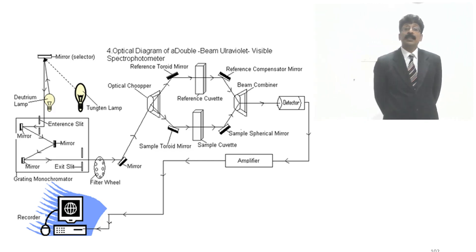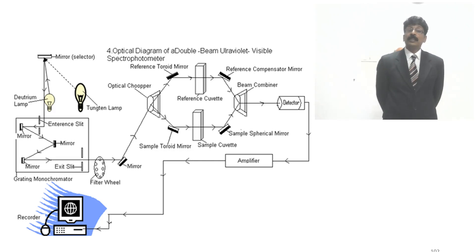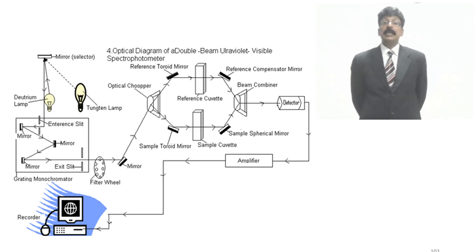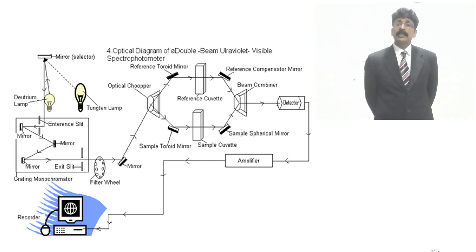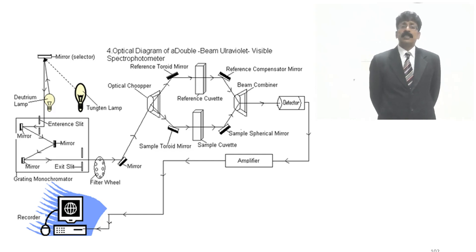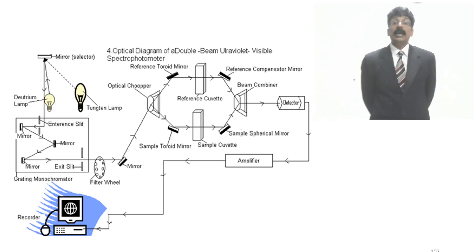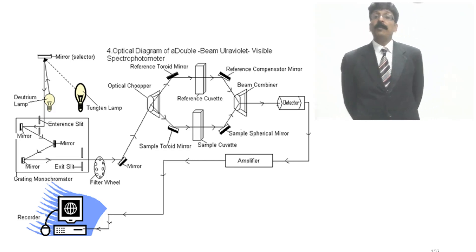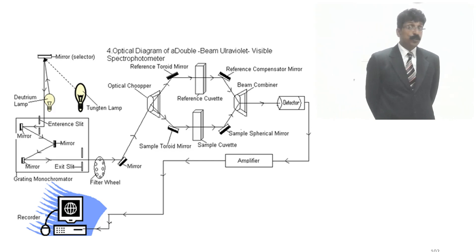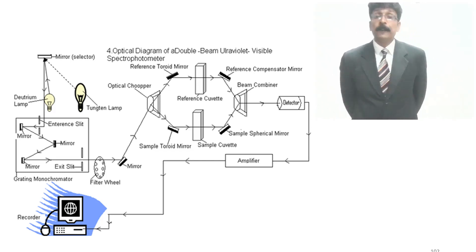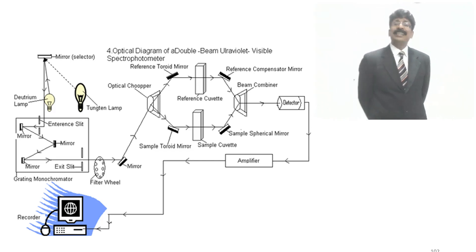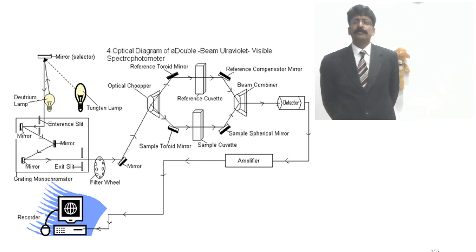After monochromatic light selection using the grating, the beam enters the sample cell — usually 1 centimeter path length. Both sample and reference beams reach the detector, which is usually a photomultiplier tube. Amplification and computerized processing then determine the concentration.